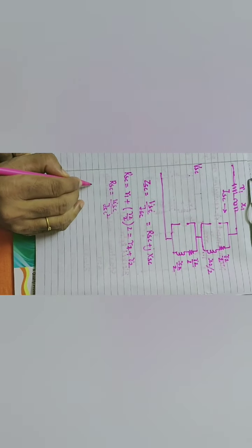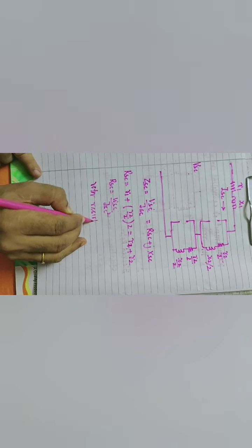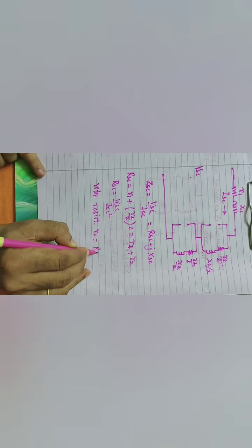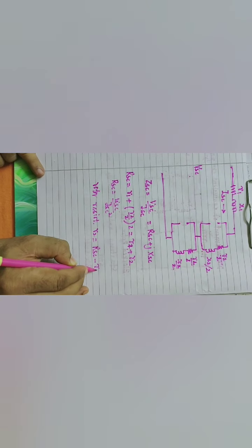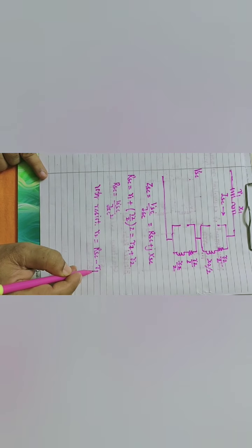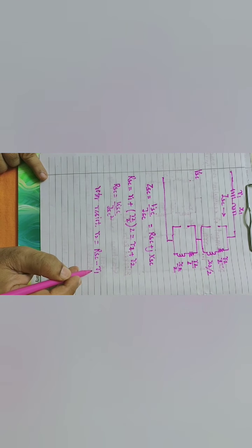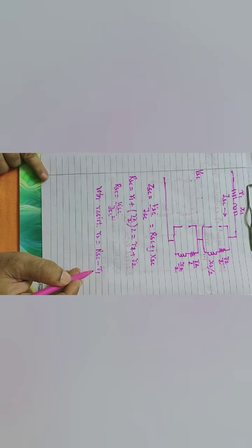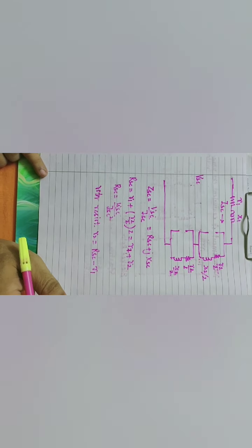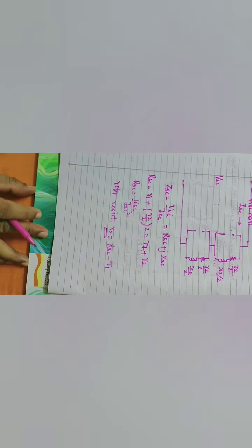From RSC, rotor resistance R2 is RSC minus R1. R1 is the main winding resistance. To determine R1, we have to conduct stator resistance test, from voltmeter ammeter readings, voltmeter ammeter method. R1 we have to determine separately, taking stator resistance. So this way we determine rotor resistance.